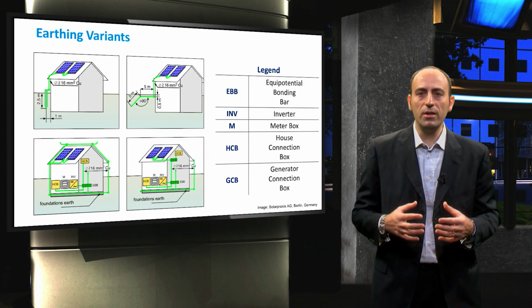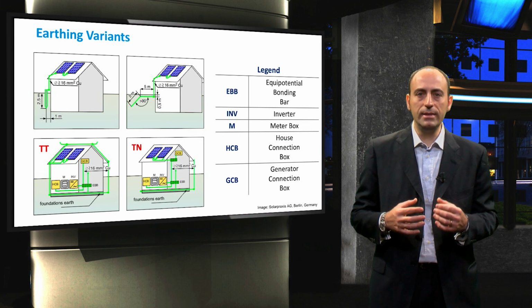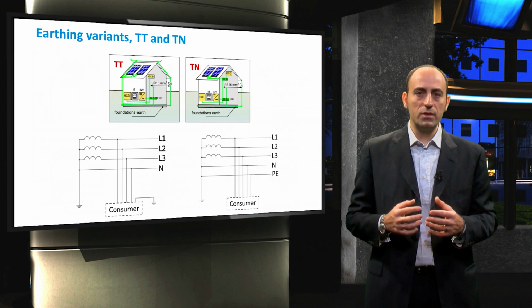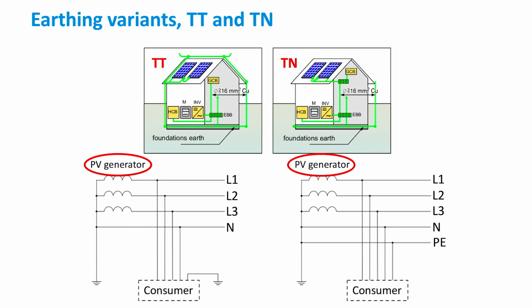These 2 arrangements are defined by the international standard as TN and TT, and now we will see why. The first letter, T, indicates the connection between earth and the power supply equipment, which is the PV generator. Therefore, T means that the generator is directly connected with earth. Then the second letter indicates the connection with the electrical devices being supplied. Therefore, in a TN earthing system, the protective circuit conductor of the consumer's electrical installation is via the protective earth cable supplied by the electricity network. On the other hand, in a TT earthing system, the protective earth connection of the consumer is provided by a local connection to earth, independent of any earth connection at the generator.